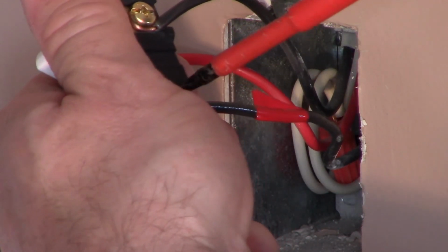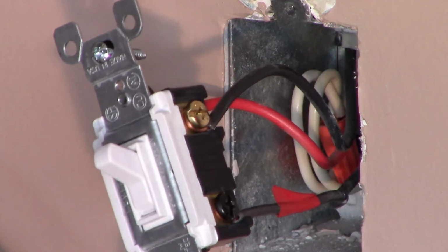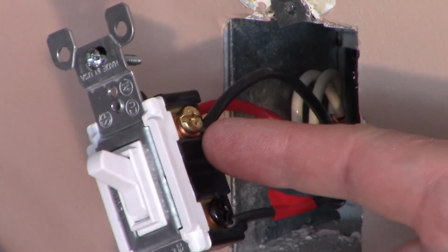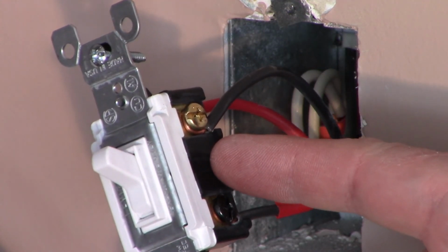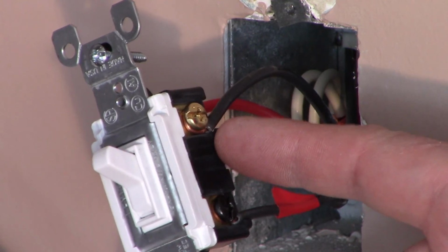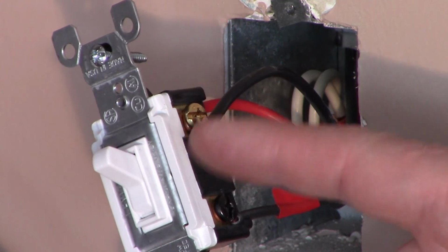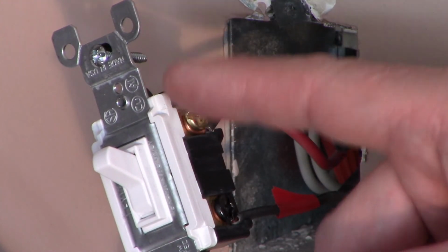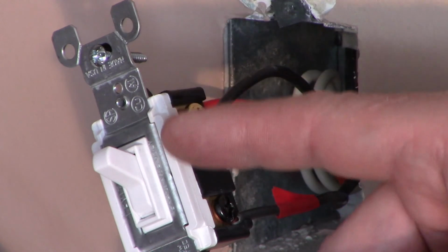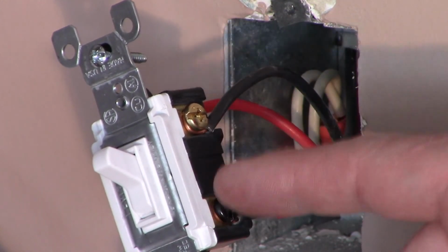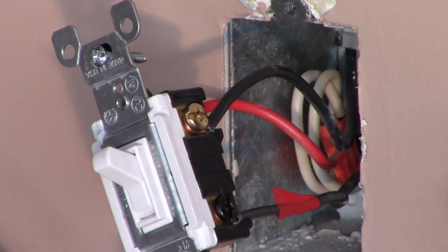1, 2, and 3. I'm just going to stop here and talk about terminating wire on these things. In our first video, we talked about aluminum wiring. If you have aluminum wiring in your house, we also talked about that you need a very special switch for that. One that's stamped with CO/ALR, copper aluminum revised. That's the spec given to switches which are allowed to accept aluminum wiring.